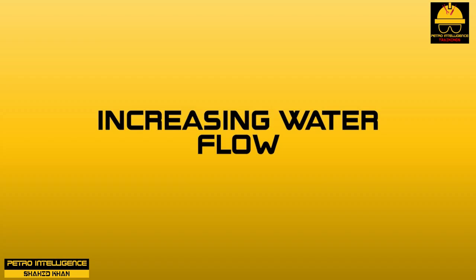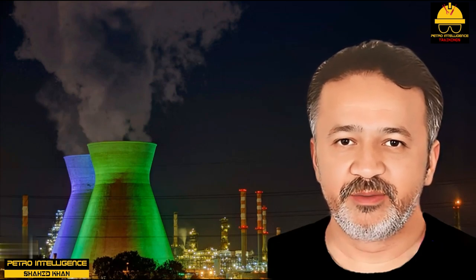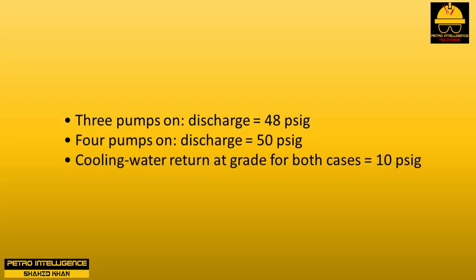Combating hydrocarbon leaks and improper water chemistry should minimize the need for online acid cleaning. Increasing water flow: your cooling tower basin is likely served by a number of circulating supply pumps. You may have observed that putting an additional pump online does very little to increase the combined pump discharge pressure — this means the total water flow has not increased significantly.